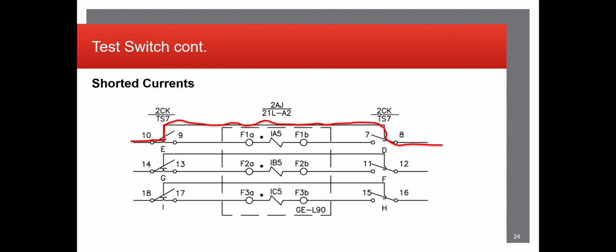The line shown above each of the current knife switches is pretty much the shorting block that we discussed earlier in a schematic sense. It shows that the knife switches should have shorting block capabilities, especially for the CT circuits.